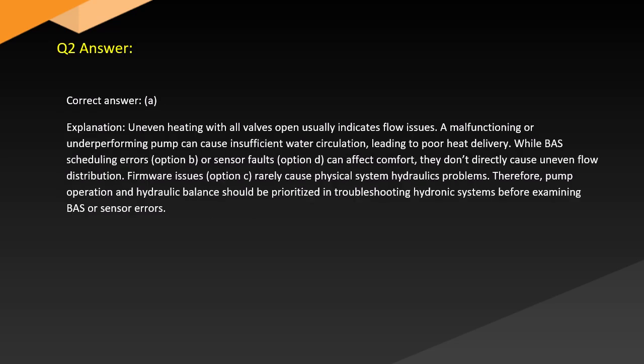Answer. Correct answer: A. Explanation. Uneven heating with all valves open usually indicates flow issues. A malfunctioning or underperforming pump can cause insufficient water circulation, leading to poor heat delivery, while BAS scheduling errors, option B, or sensor faults, option D, can affect comfort. They don't directly cause uneven flow distribution.